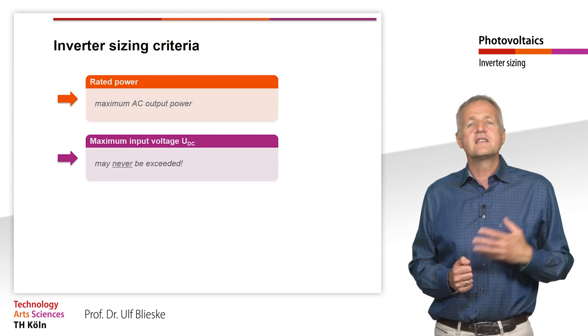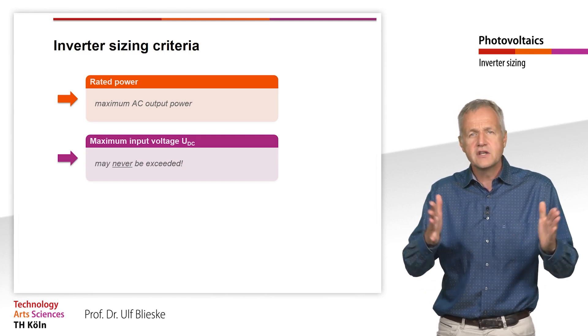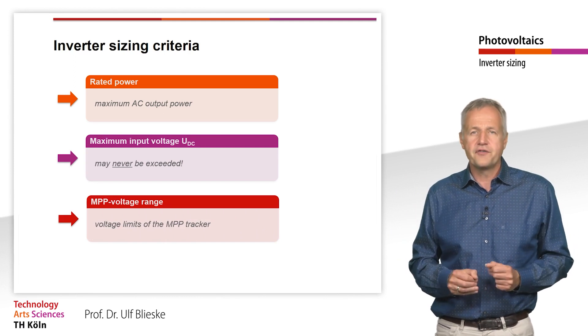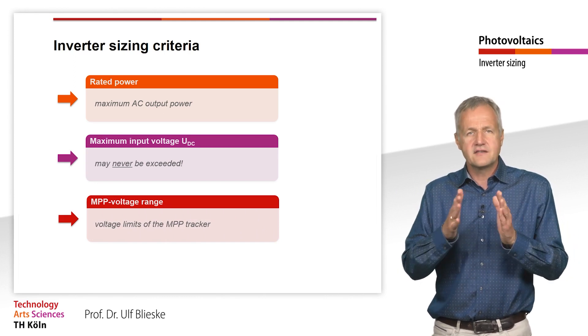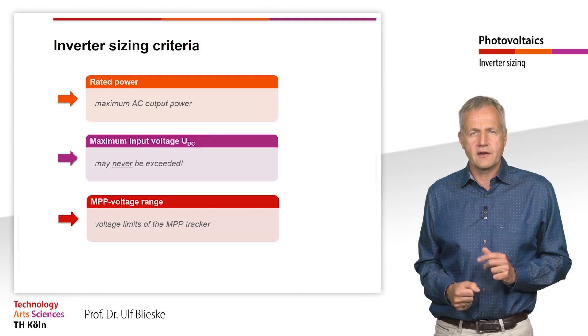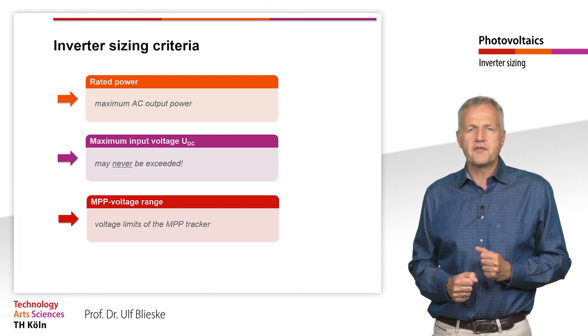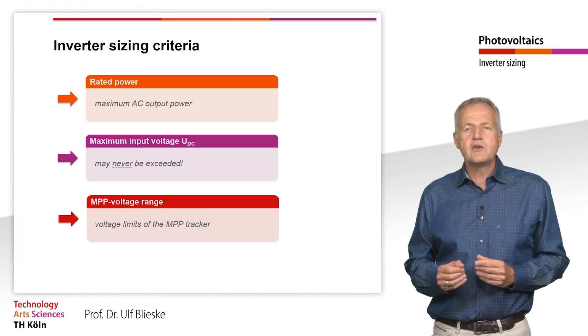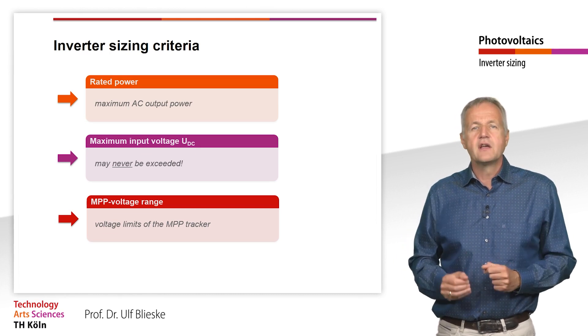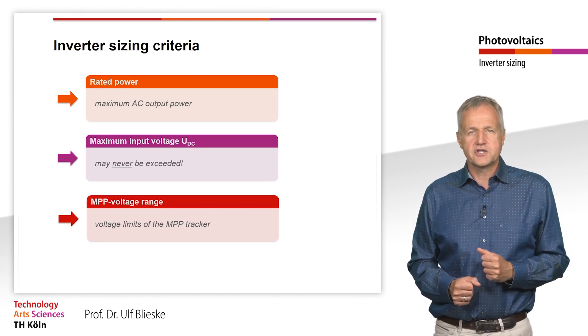This is the only criteria that can lead to the destruction of the inverter if it is incorrectly sized. In addition, there is a certain input voltage range in which the MPP tracker of the inverter can find and set the MPP of a string. The MPP of the solar generator should be within this voltage range in all operating conditions.